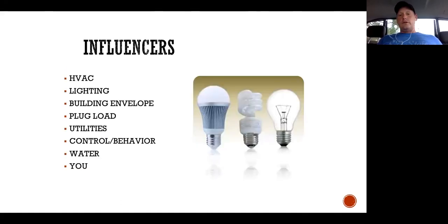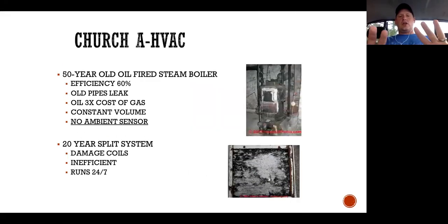So if we briefly walk through an energy audit, our influencers are HVAC, lighting, envelope, plug load, utilities, etc. I'll walk through two churches and look at HVAC. This happens a lot—I walk into seminaries and churches and see older systems, like an oil-fired steam boiler. Sometimes you have what you have, but the efficiency right off the bat of an oil-fired steam boiler is 60%. You have leaky pipes, which means you lose another 10 to 20%, so now you have an HVAC system operating at 50% efficiency.